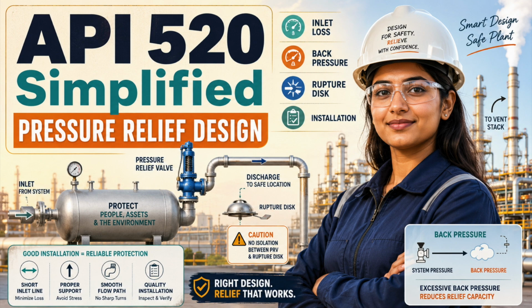Burst pressure depends on disc temperature. The temperature at the disc when it bursts may not equal the vessel design temperature, normal operating temperature, or general process temperature. If the temperature basis is wrong, the disc may open at a pressure different from what you intended.